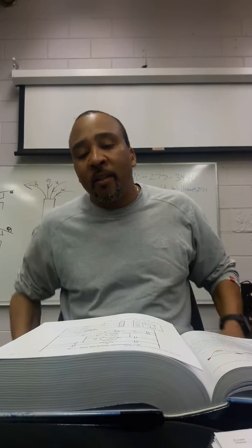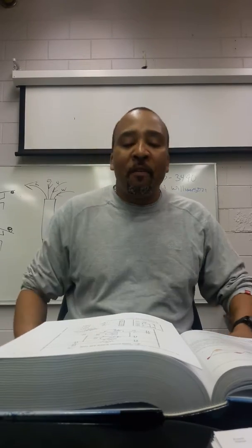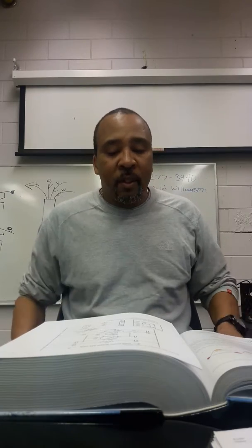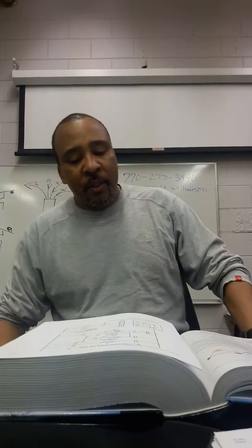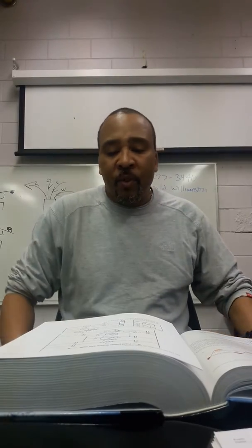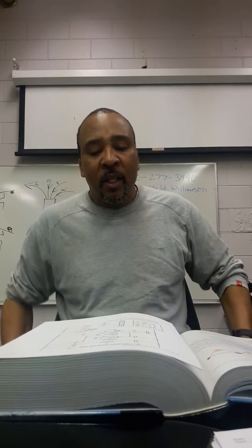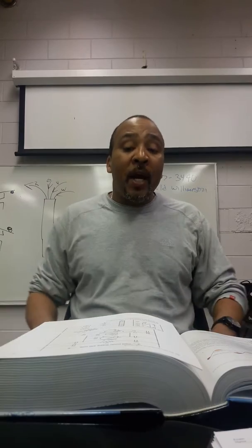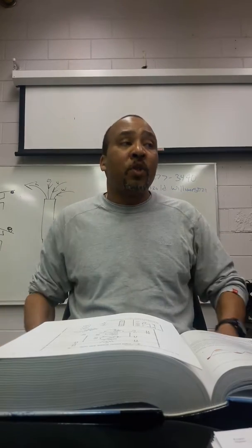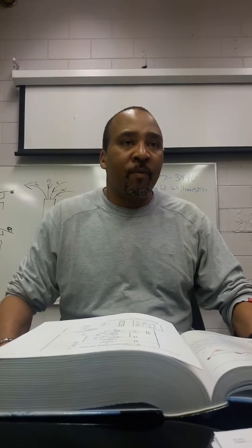The jackleg will say, well, shoot, any of this stuff could be bad. I'm going to get every part in this circuit. Now, if he got every part in this circuit, he would need the transformer, the thermostat, the indoor fan relay coil and contacts, and the fan motor. Not the fan switch, because the fan switch is only for low speed. We trying to get this unit to work on high speed.